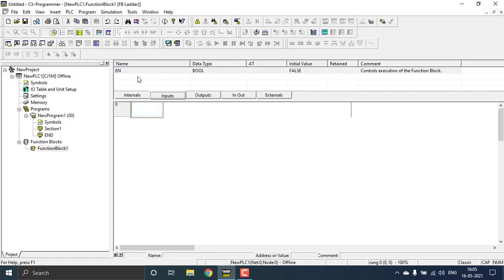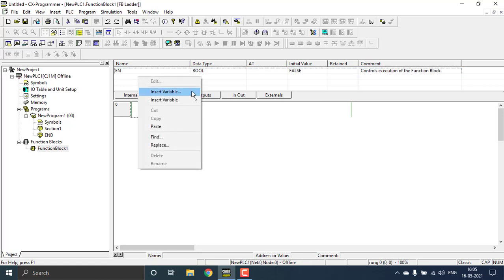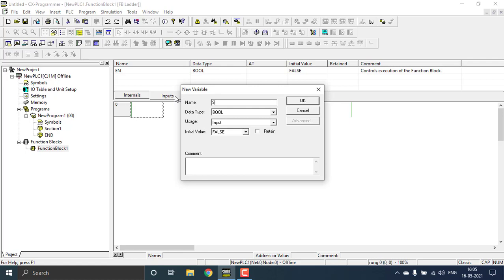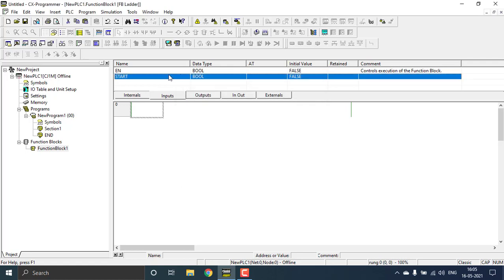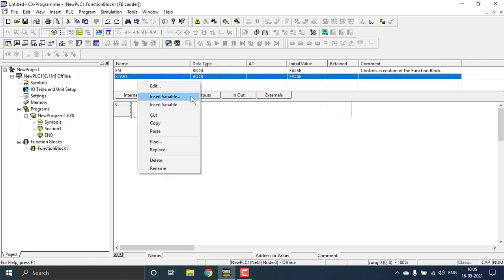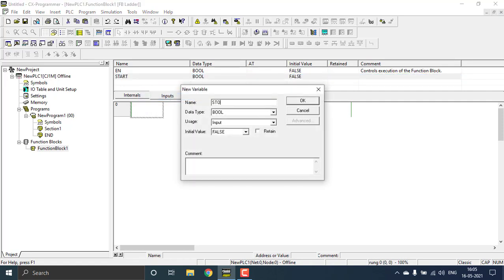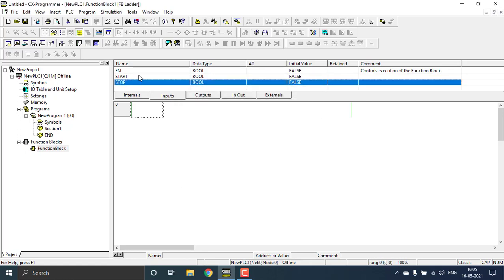Go to the inputs — I just need two inputs: one will be 'start' and another will be 'stop'. Right-click and insert a new variable. These types of variables work inside the function block. The data type will be Boolean, usage will be Input, and the initial state will be False. Hit OK, then insert another variable for 'stop'. Note that normal input addresses cannot be given to function blocks, which is why I am creating my own local variables.